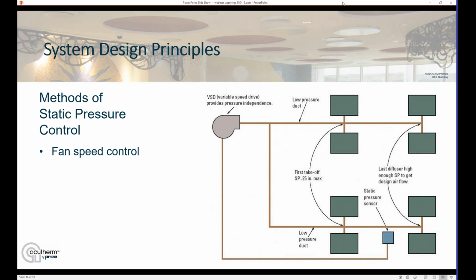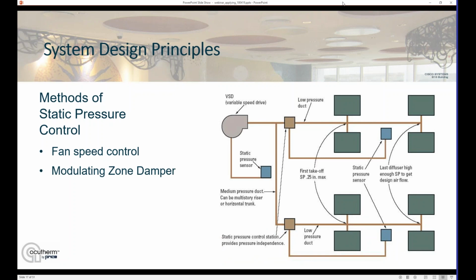And then as the diffusers start to open and close and work toward their minimum, we're going to locate a static pressure sensor downstream in the ductwork, usually 2/3 to 3/4 of the way downstream. And that's going to directly control our fan speed. So as the diffusers start to close toward minimum, the fan slows down and prevents the pressure from building up. And when the diffusers open up again, the fan can ramp back up and keep that pressure available for the diffusers to provide the air volumes they need. That method is not always applicable to larger buildings, large footprints, or multi-story buildings.